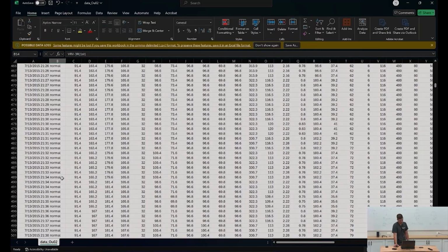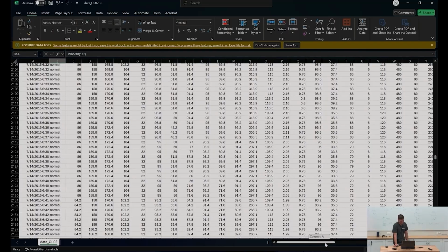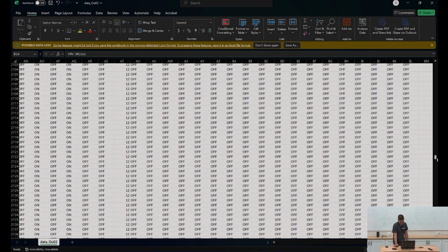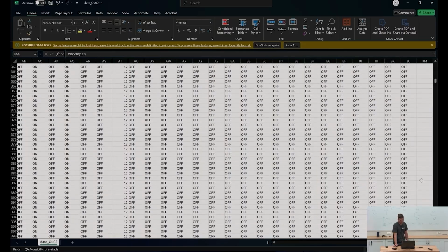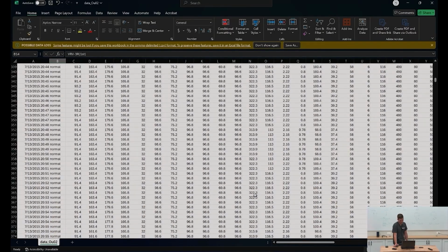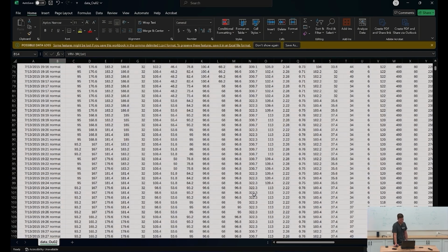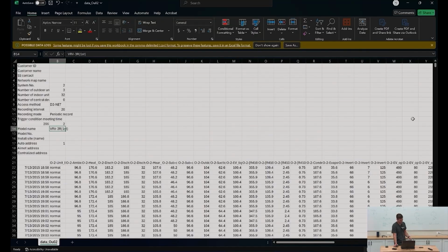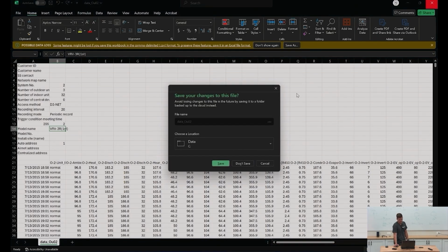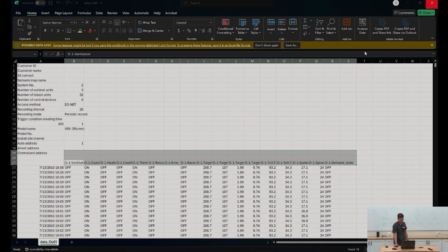You can say, well, yeah, I'll just go in here and I'll find the problem really quickly. This is worse than service check. There's no graph. Wait, let me just scroll over to see that one number. Did any of my, and you know, there's better versions of this that other people have made out in the field where it's a macro too, but what it does is it goes through and it highlights high suction superheat, high discharge superheat, high subcooling, low sub. It changes the columns colors, and then it also filters them for what safeties turn on and off. Don't save. So I verified the orders are correct.